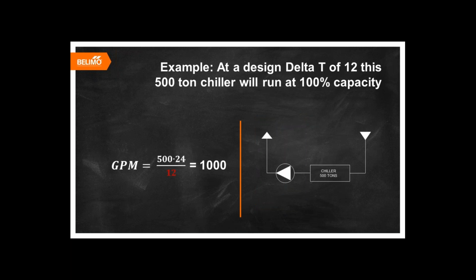Here is a simple example of improper staging of chillers due to low delta T. For this example, we would have a 1,000-ton chiller plant with two 500-ton water-cooled chillers. Our design delta T is 12, and our maximum flow at each chiller is 1,000 GPM. At the design delta T of 12, one chiller is able to meet the load and run at maximum efficiency, as you can see in this example.